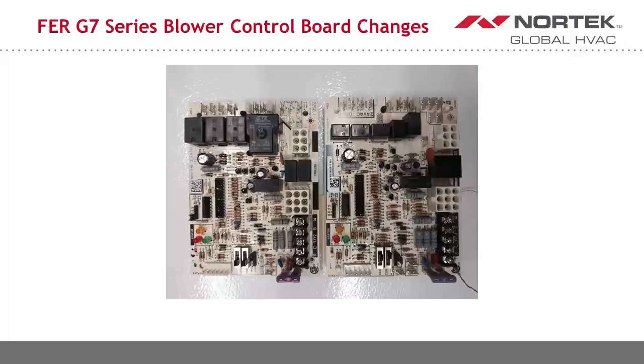Another frequently asked question is what some of the similarities and differences a contractor may expect for an FER compliant unit. For a furnace control board, the interaction and speed select switch remain the same with a low, medium high, and high speed selection available. The minor differences you will see on the control board will include low voltage relays in place of the existing high voltage relays. Further instructions, including wiring the 5th speed on the blower motor and blower curves, will be laid out in the unit's installation instructions.